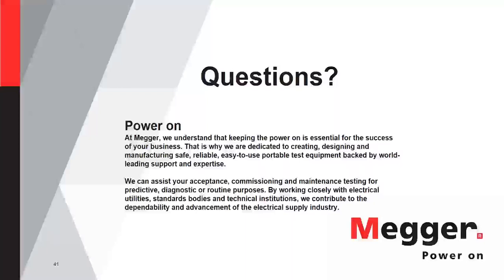Really, NERC doesn't recommend any time. This would be more oriented to what you have in the system. If you have enough time to have a battery out of operation for 8 hours, I would definitely recommend running the 8-hour test. It is kind of the nominal rating, and as I said, batteries might have some efficiency issue depending on the level of current that you use, which will obviously impact the time of the test.